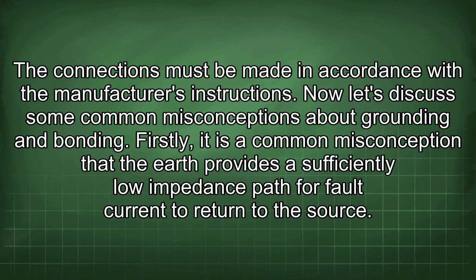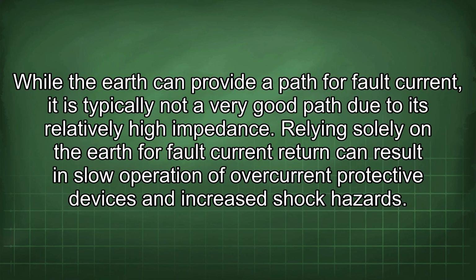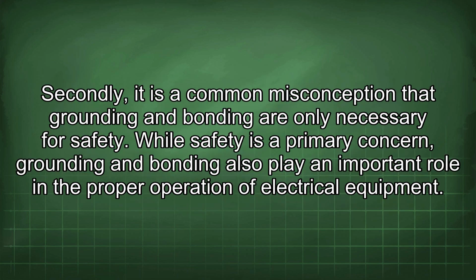Now let's discuss some common misconceptions about grounding and bonding. Firstly, it is a common misconception that the earth provides a sufficiently low impedance path for fault current to return to the source. While the earth can provide a path for fault current, it is typically not a very good path due to its relatively high impedance. Relying solely on the earth for fault current return can result in slow operation of overcurrent protective devices and increased shock hazards. Secondly, it is a common misconception that grounding and bonding are only necessary for safety.